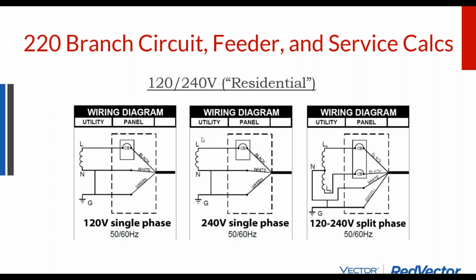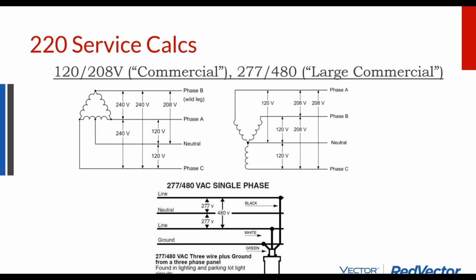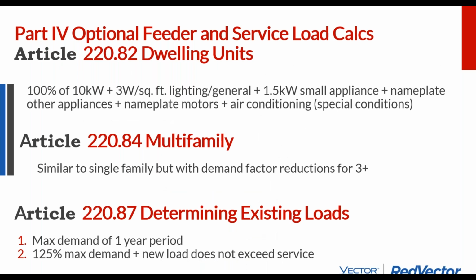Let's see, where this was useful is recently I was rewiring a hot tub, and it was on a 240 volt circuit. Is it 120/240, or is it 240 from 0 to ground? In this case it was two 120 volt lines and a ground, rather than a 240 neutral and ground. At the commercial level, you talk about delta versus Y electrical systems, and that has to do with the transformer wiring. And then all of your battery inverters and motors and equipment have to match the electrical service that you're powering.